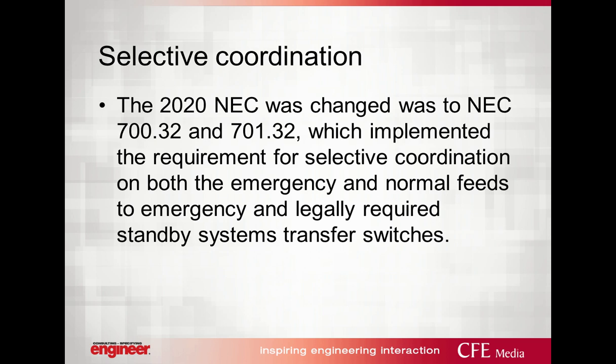Selective coordination, I touched upon that. It's now been conformed to be in both 700 and 701 under point 32 in the NEC. And selective coordination, for those of you who don't know, means that the closest device to a fault in my system is going to open first. I do not want anything upstream to open. So if I have a branch circuit that has a fault to ground, somebody faults it to ground, I want that closest breaker to open, or closest fuse switch to open, not the main and the distribution board. So it's a requirement of code. It has to be down to the 0 period of time for 700s and 701 systems.